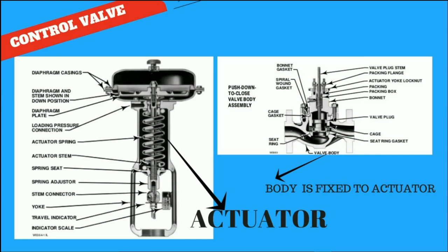Control valve is also termed as the final control element. Working principle of valve is, when variable air pressure is applied to a flexible diaphragm to oppose a spring. The combination of diaphragm and spring force acts to balance the fluid forces on the valve.